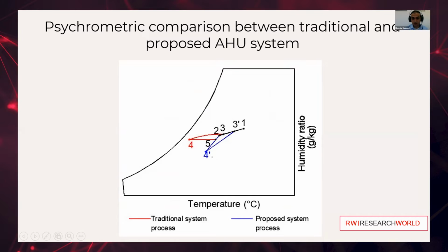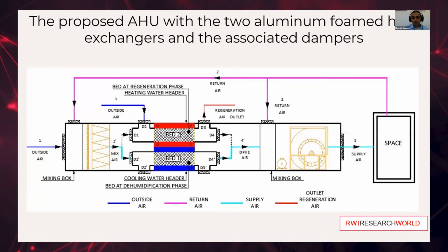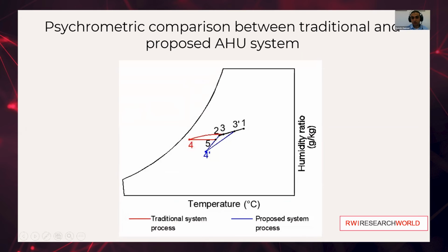Point 4' in the proposed system represents the downstream values of temperature and humidity for the bed, where this point represents the average values of outlet air temperature and humidity from the bed. In order to mix air from point 4' with the rest of the return air from point 2, point 4' must lie on the same sensible heat ratio line to 5.